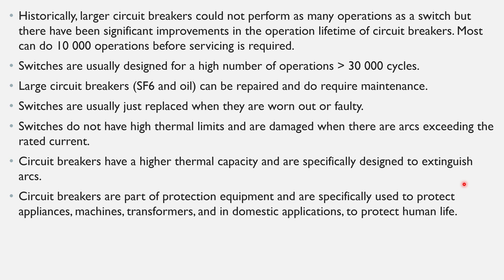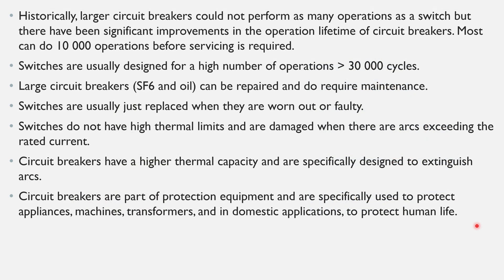Circuit breakers are designed to have a higher thermal capacity and are specifically designed to extinguish arcs. If you look at the cross-sectional view of a switch and a circuit breaker, the switch is simply contacts that rock open or closed, or two contacts pushed together. The circuit breaker is more elaborate and has an entire chamber just to deal with the arc.